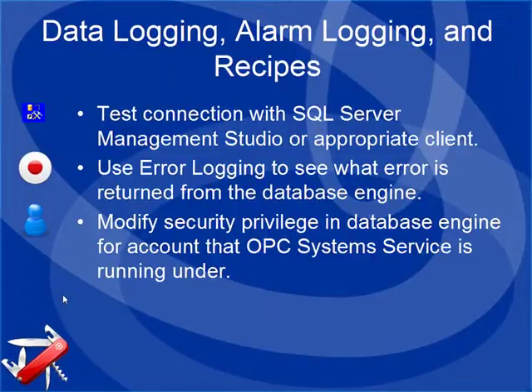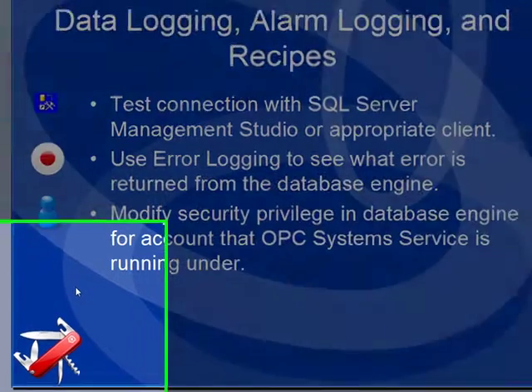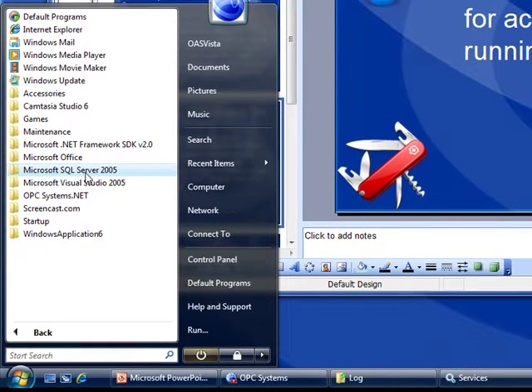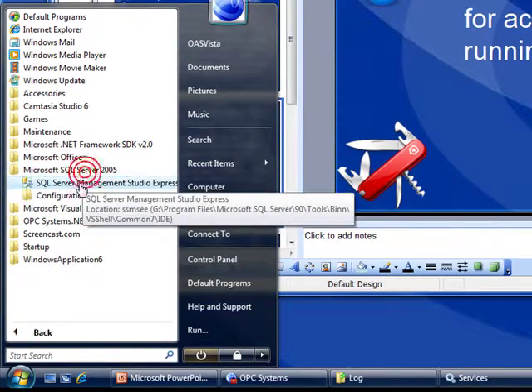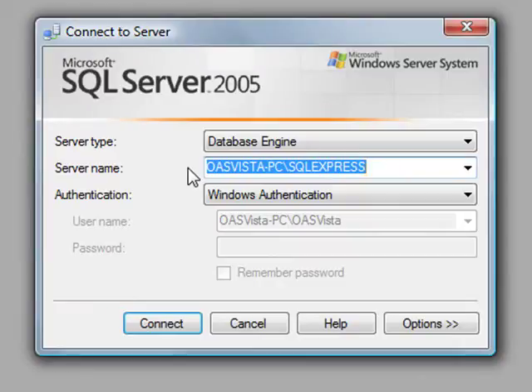Next, let's discover how to resolve common data logging, alarm logging, and recipe management problems to database engines. The first thing we might want to do is test the database connection. I will demonstrate Microsoft SQL Server with the SQL Server Management Studio. When we first connect to the database engine, we want the server name to be exactly the same as we have specified in the data logging, alarm logging, or recipe configuration.